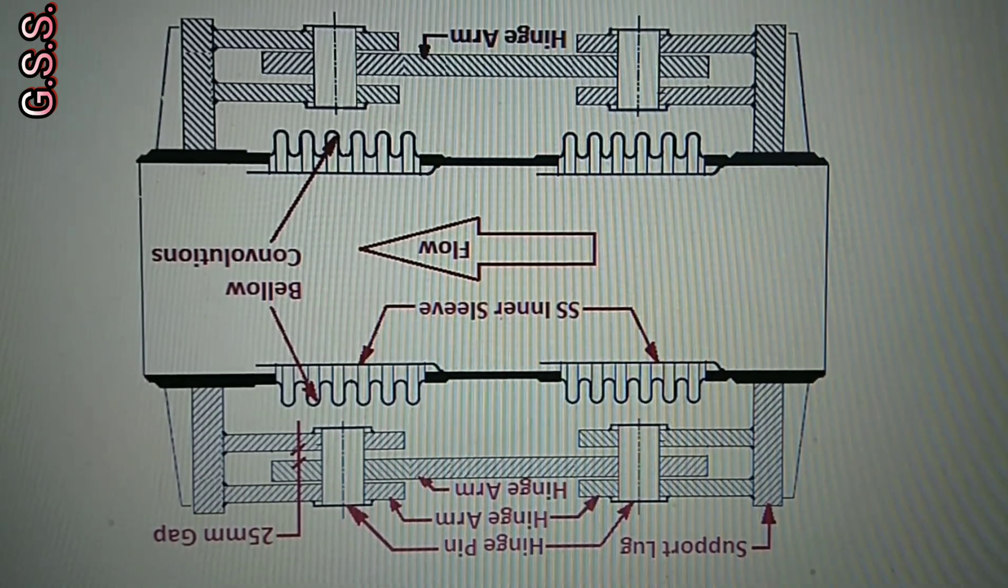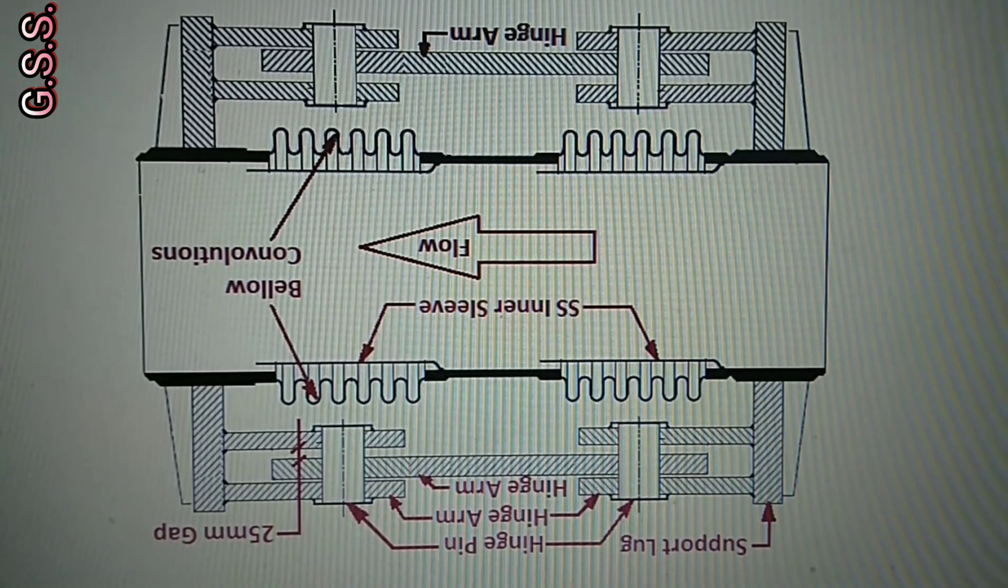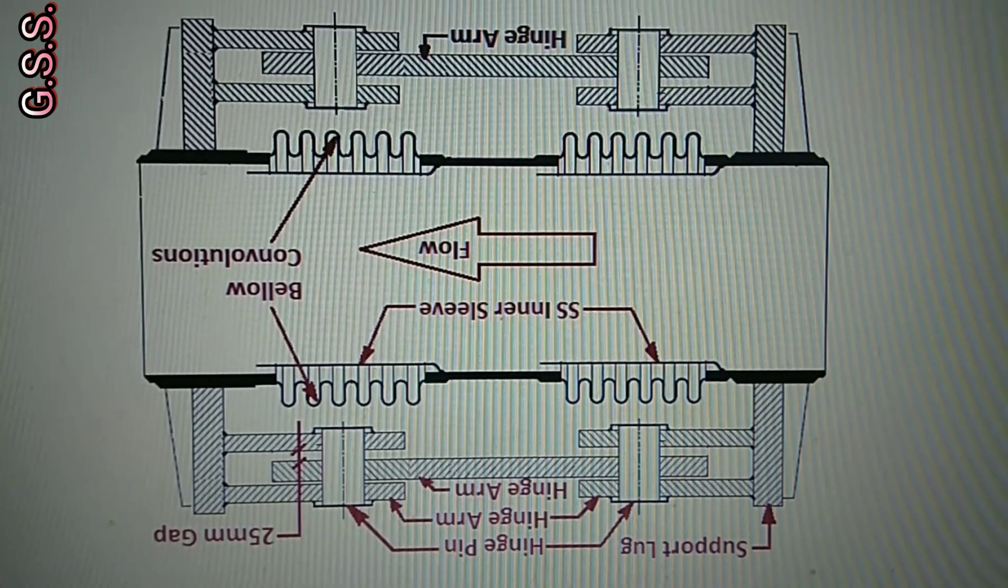Since the bellows size is 32 inch, cross sectional area of the bellows is about 5000 centimeter square and if the internal pressure is 10 kg per centimeter square gauge, then axial pressure thrust will be 5000 into 10 equals to 50000 kg.